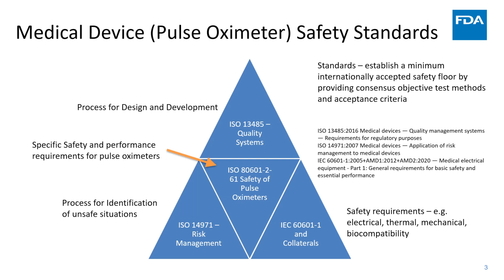Now, they also have to make good decisions within that design and development process. And that's where this family of 60601 comes in. IEC 60601 is the requirements. You can see medical electrical equipment, general requirements for basic safety and essential performance. And so it establishes acceptance criteria. For example, how hot can your probe be, right? And how accurate should your probe be?